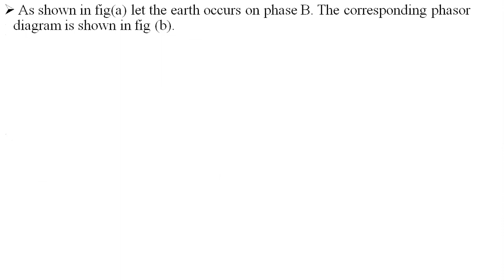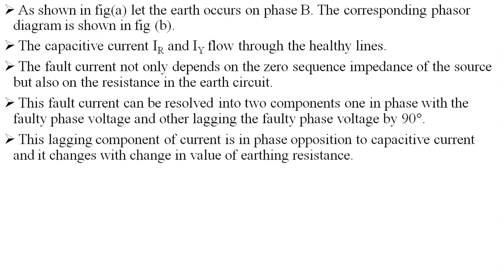The figure shows an earth fault occurring on phase B, and the corresponding capacitive currents IR and IY flow through the healthy lines. The fault current depends not only on the zero sequence impedance of the source, but also on the resistance in the earth circuit. This fault current can be resolved into two components: one in phase with the faulty phase voltage, and the other lagging the faulty phase voltage by 90 degrees. This lagging component is in phase opposition to the capacitive current, and it changes with the value of the earthing resistance. Thus, the resistance is designed in such a way that during faults on any phase, a current equal to the full load current of the largest alternator or transformer flows in the earth resistance, which will keep the overvoltages within limits.